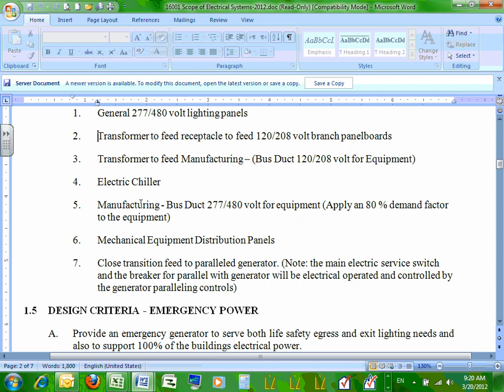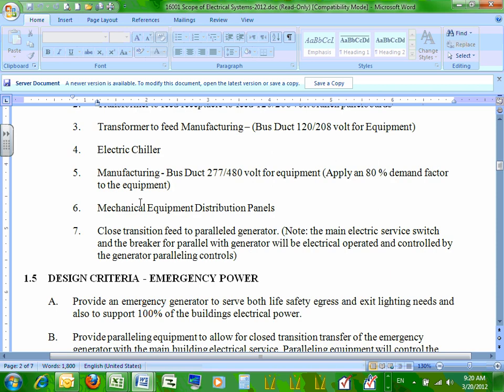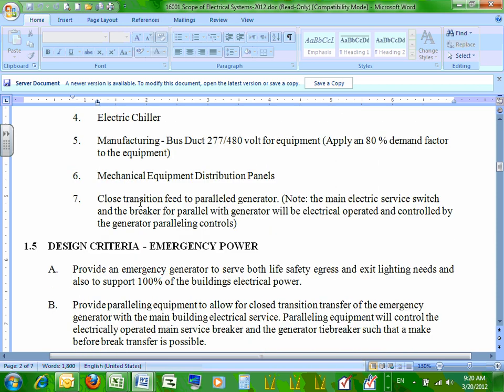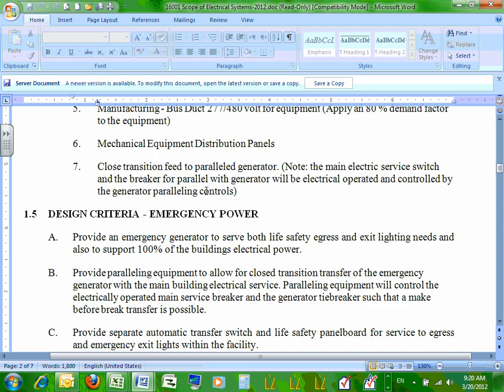And I am suggesting that you can apply an 80% demand factor on the equipment in this equipment list as you get involved with your design. And then we'll have some mechanical equipment distribution boards going back to the switchboard. Talking about closed transition feed to parallel the generator, the electric service switch and the breaker for the parallel generator will be electrically operated and controlled by the paralleling gear.